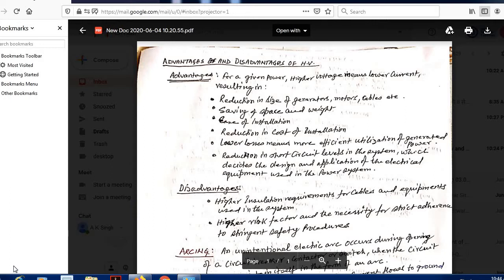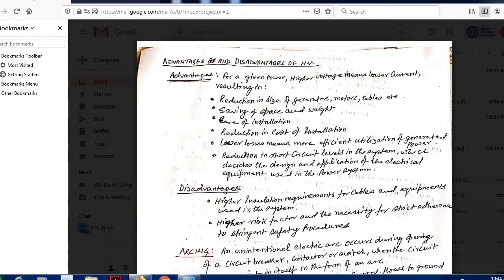So we went for high voltage, and we saw with the example that for a particular power, when we increase the voltage, the current is reduced. Now, what are the advantages we have? For a given power, higher voltage means lower current, resulting in reduction in size of the generator, motor and cables, saving of space and weight, which is again a big factor for a merchant vessel, because if there is a saving of space and weight, then the light weight of the ship will be less, and the ship can carry more cargo and earn more freight.